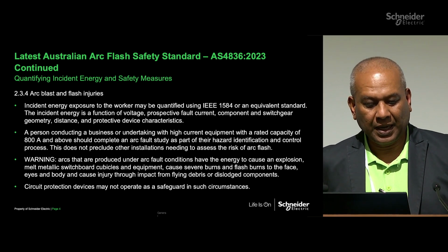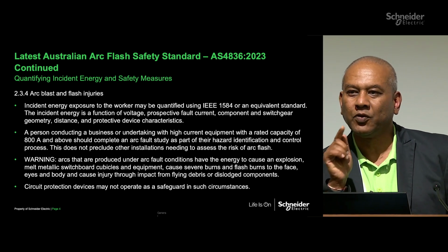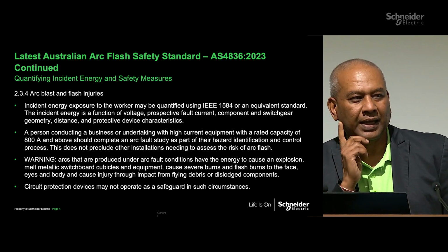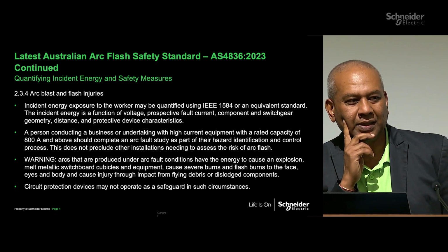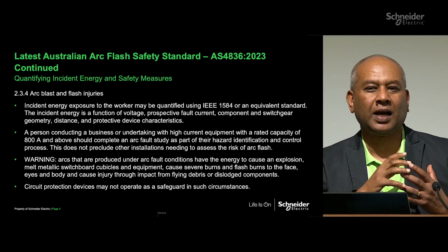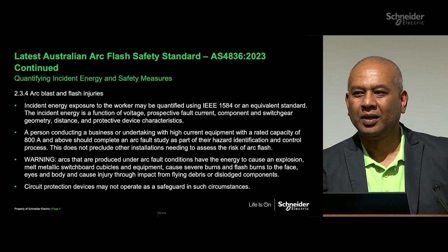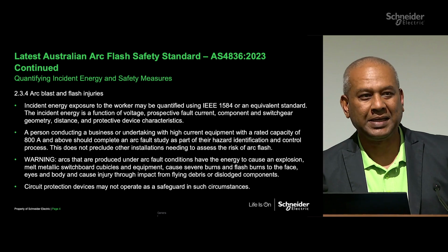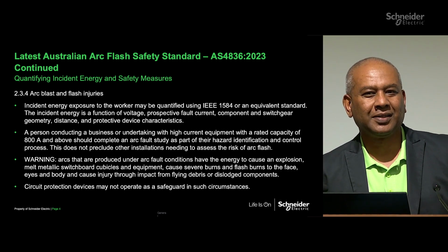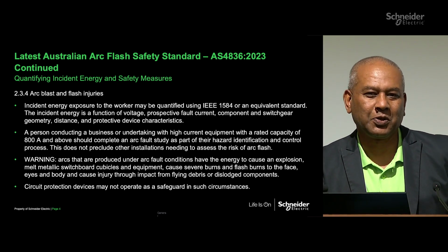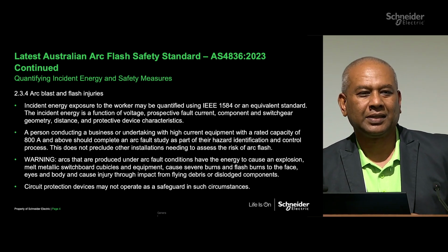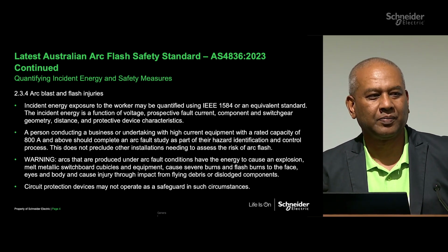The main thing in the arc flash concern, I think some of you may have attended a prior session which one of my colleagues delivered, on internal arcing, which was more about partial discharge. If you leave partial discharge to run its course, eventually it will lead to an arc flash, maybe after many years. So we don't want to do that. That's why that session was useful, because we now have technology to detect partial discharge and prevent arc flash from happening.